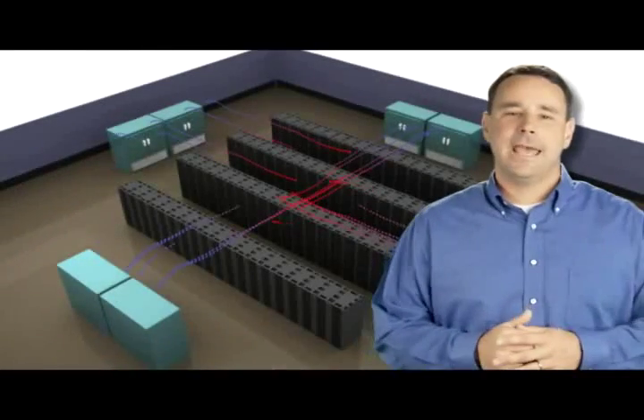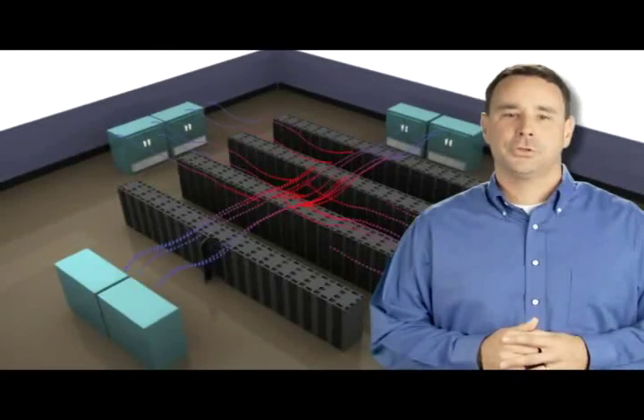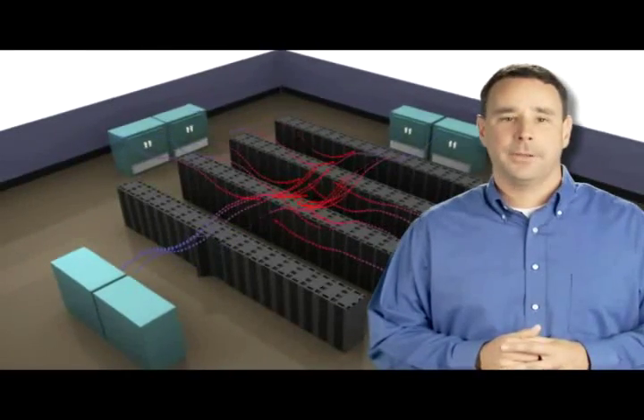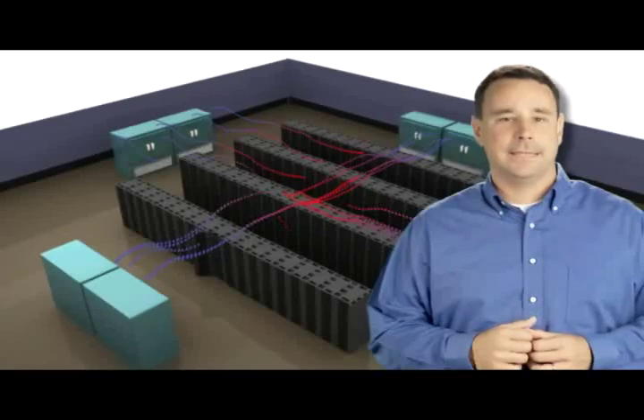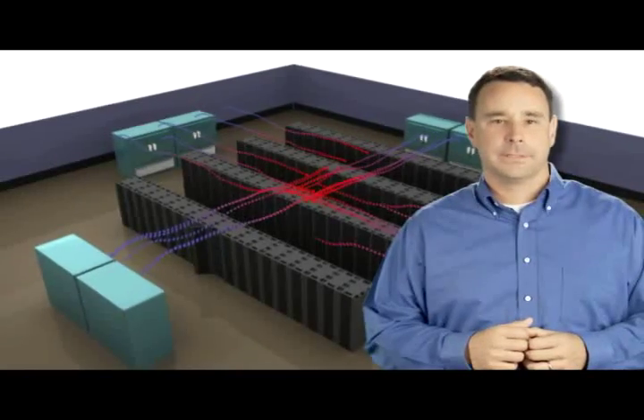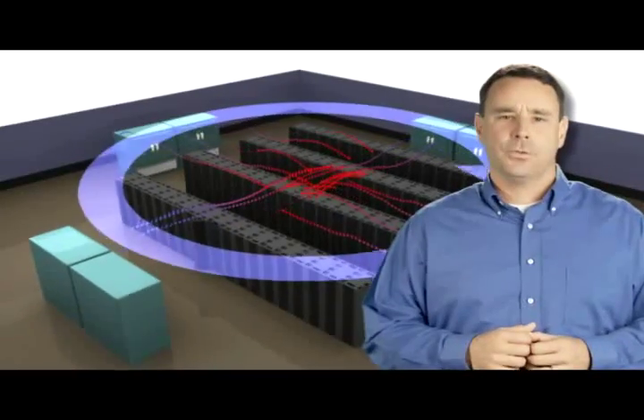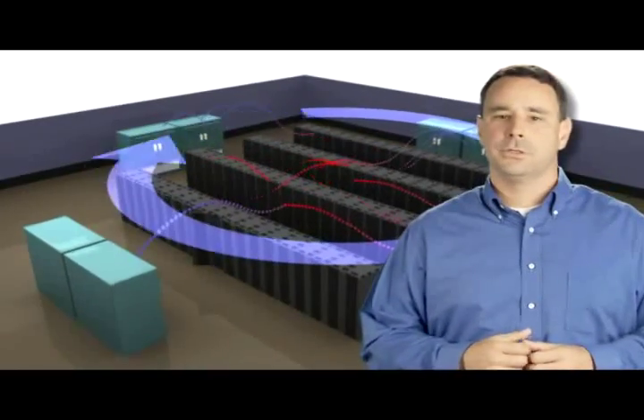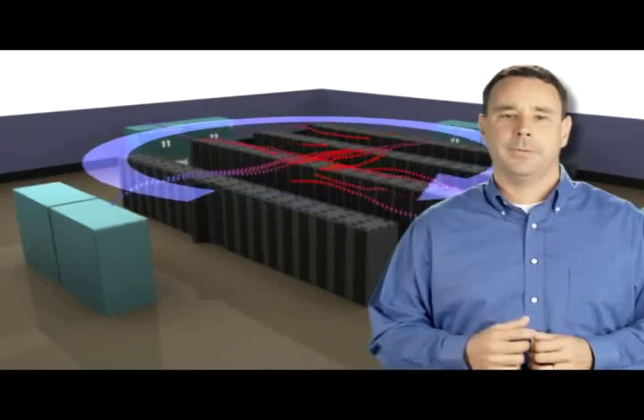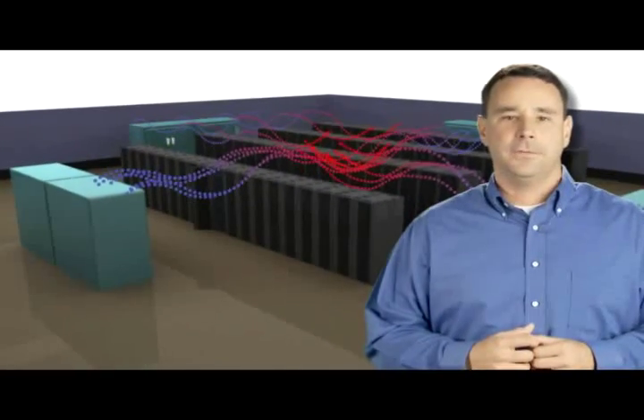In this example of the traditional cooling setup, the air conditioning units are at the ends of the rows. This 'circle the wagon' approach doesn't work - cooling never reaches the problem areas deeper in the aisles. If you lower the set point, the same thing happens, plus now you're over-cooling the ends of the rows.